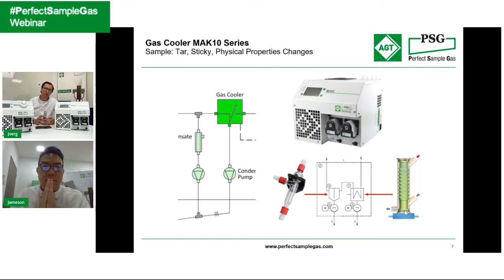If you imagine putting the pre-condensate inside the gas cooler instead, we get a stable temperature, much cooler than the outside ambient. Now the sample comes in and collects these impurities or contaminants. Same philosophy, but if you put it inside the cooler it's much more effective. At the same time it removes water, not only the contaminants. You have two functions at once.